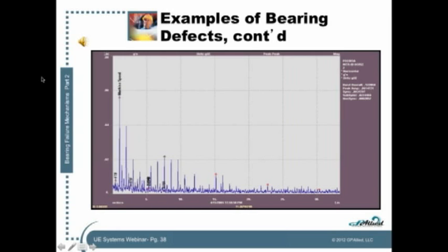Now, hopefully what you heard from that is the total volume of the sound was down, and I didn't mess with my computer or anything. Total volume of the sound was down, but the pattern was very distinctive, and the pattern was quite rougher than the first one you heard. So these two are two really nice examples of failure propagation from zone 1 into zone 2 on the P-F curve.